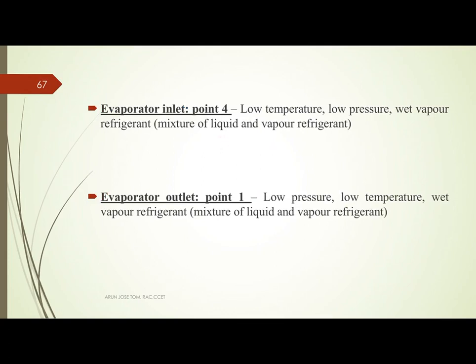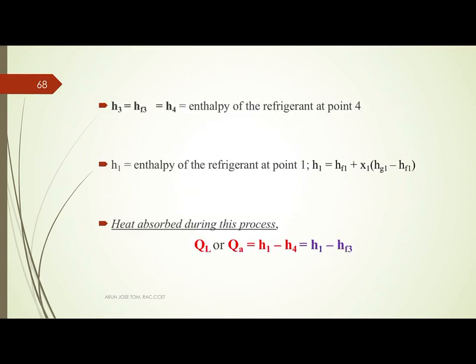The refrigerant condition at the inlet of the evaporator is low temperature, low pressure, wet vapor. The exit from the evaporator is also low pressure, low temperature, wet vapor refrigerant. To calculate how much heat is absorbed by the evaporator, we calculate enthalpy at points 4 and 1. H4 equals H3 equals HF3. H1 equals HF1 plus x1 times (HG1 minus HF1). Heat absorbed during this process is H1 minus H4, or H1 minus HF3.